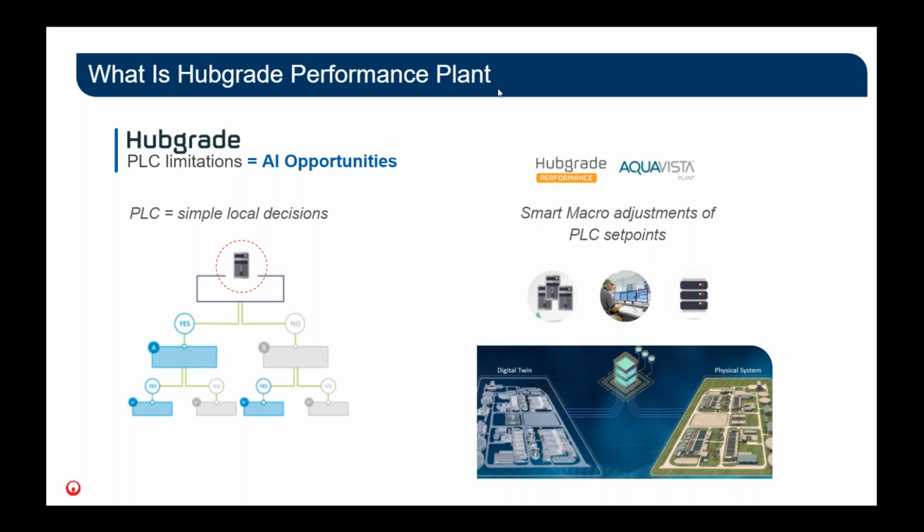You can have a lot of if-then sort of statements and PID loops and everything. But in today's control environment, you can really fine-tune things a lot more with digital twin technology and automated set point adjustment that is coming out of algorithms that receive various inputs in real time from the treatment facility.